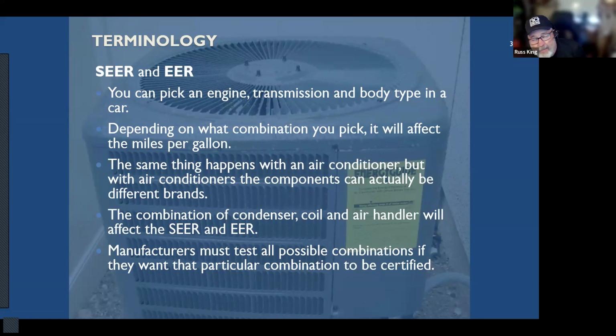And so it's gotten kind of complicated lately. I remember way back in the day, all they cared about was the SEER rating of the condenser with its most common coil match, and they would put a sticker on there, and that's all you had to worry about. But now, because it's getting quite difficult to make houses comply with the energy code, we have to be much more precise on that number. So now you've got to go to the AHRI website and you've got to know the condenser, the coil, the air handler model number, if it has a TXV, if it has a time delay relay and all this other stuff. And then it will give you a very precise efficiency number for that combination of equipment. Okay.